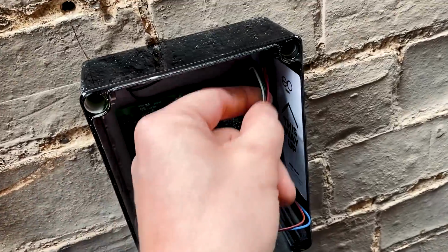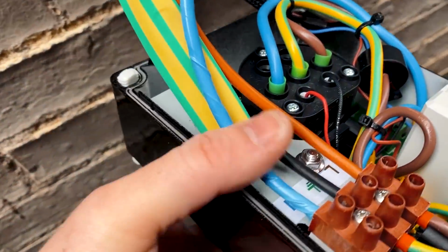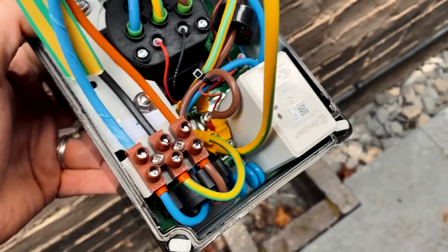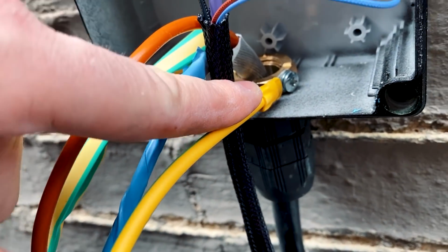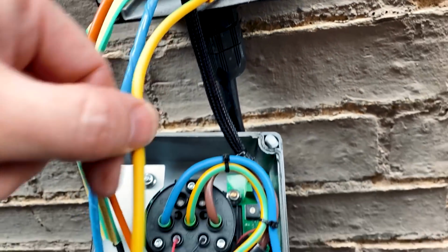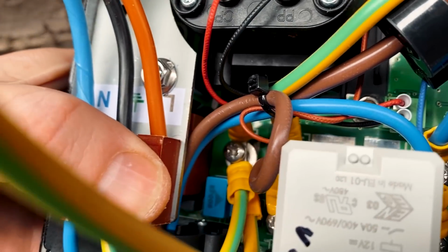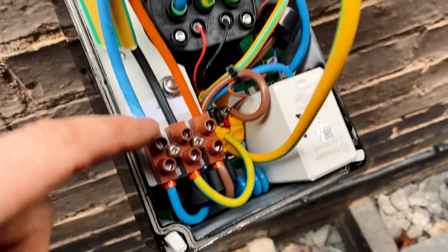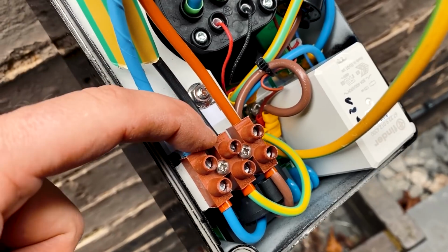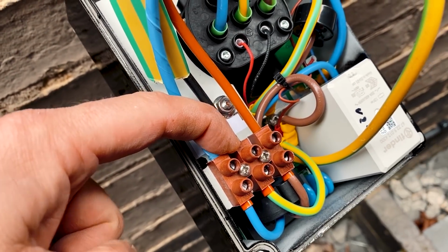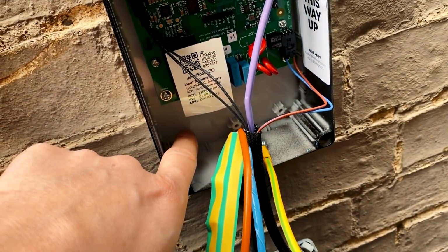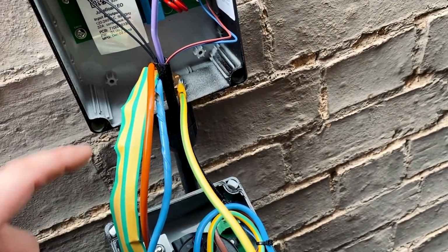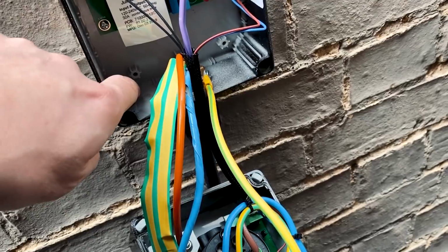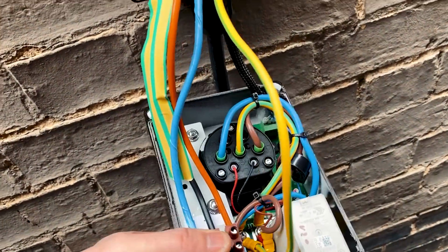So I've got all these flying leads connected. My main cable is connected into the mains terminals there. I've done a flying lead from the earthing nut on the steel wire armoured, and run that down into the earth terminal at the bottom, because that earth terminal is only big enough for one cable. The other thing I could have done is put a wire in the back of the box and split off one to the flying lead, one to the mains, and one to here, but I just decided to do it this way this time.